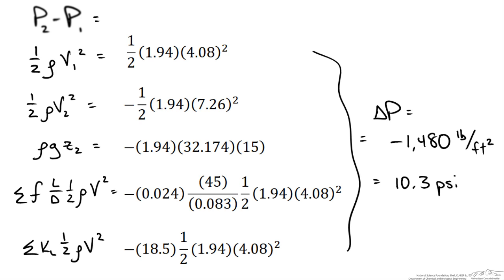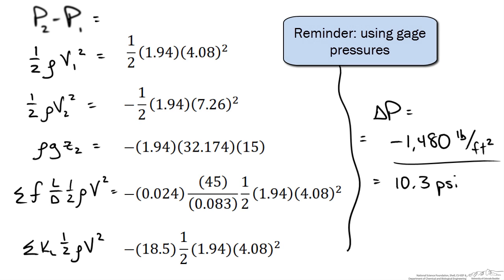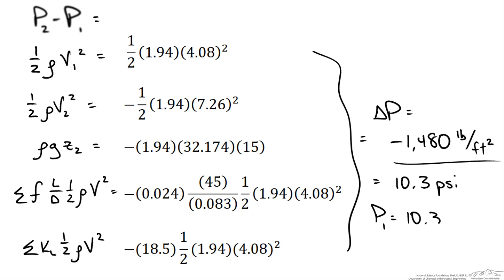Which is a much more reasonable value when talking about the pressure loss through a piping system such as the one in the problem statement. Now whether it is negative or positive doesn't really matter as long as we understand that it is a pressure drop and that the pressure is higher at the inlet than it is at the outlet. Now if we wanted to calculate what P1 was we would just need to know P2, which in this case is just exiting to the atmosphere so P2 is equal to zero. Which means that our inlet pressure for our system is also 10.3 psi.